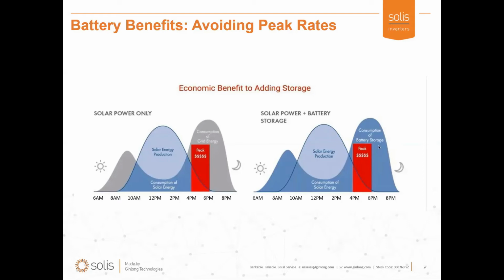But with energy storage, the PV system can charge the battery with excess power during the daytime, so that in the evening, the battery can discharge energy instead of power having to be purchased from the utility. For this reason, it's important for the inverter to have a programmable time of use function that allows customers to set their own energy discharge schedule based on their utility company.